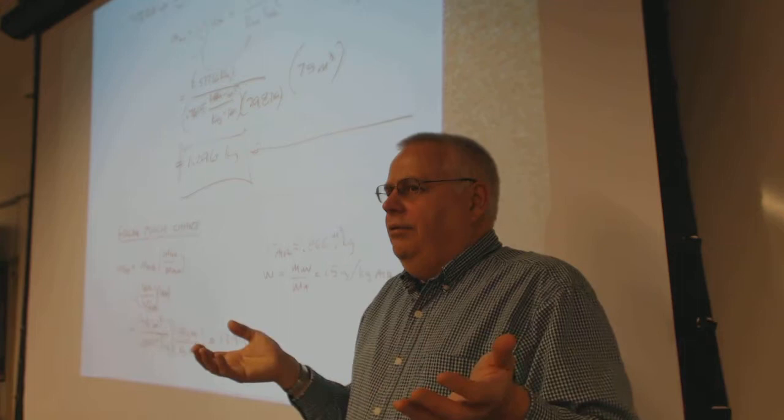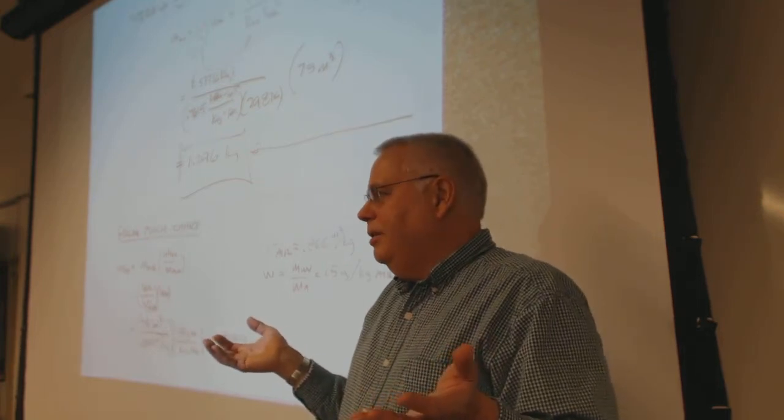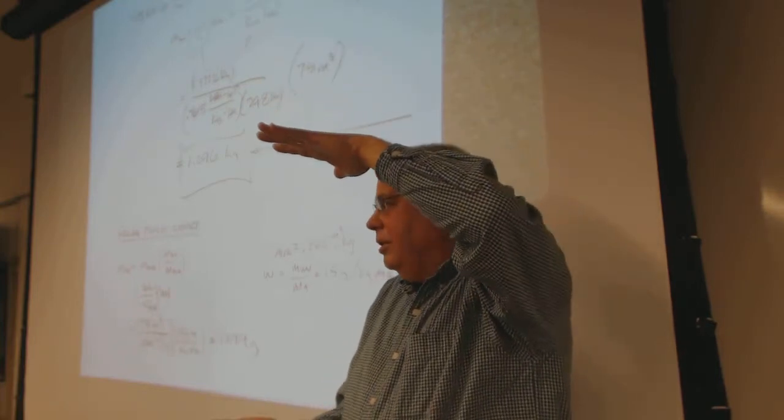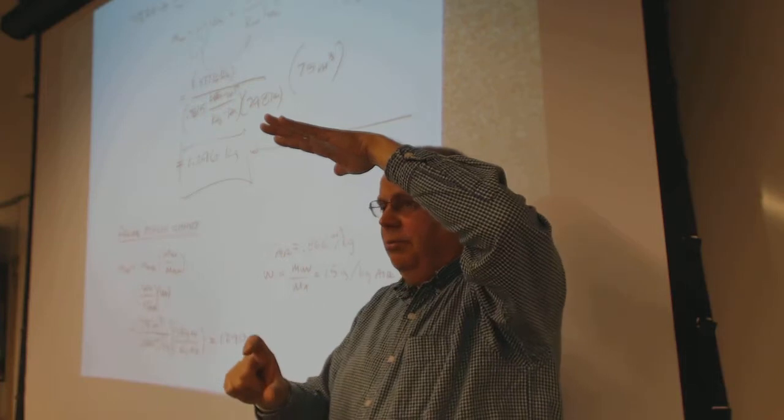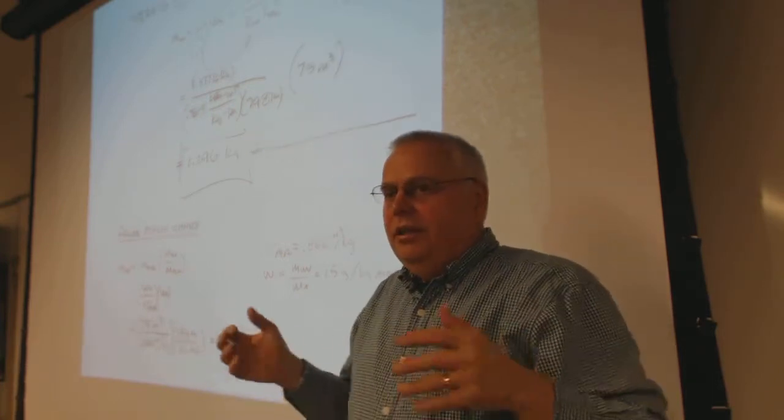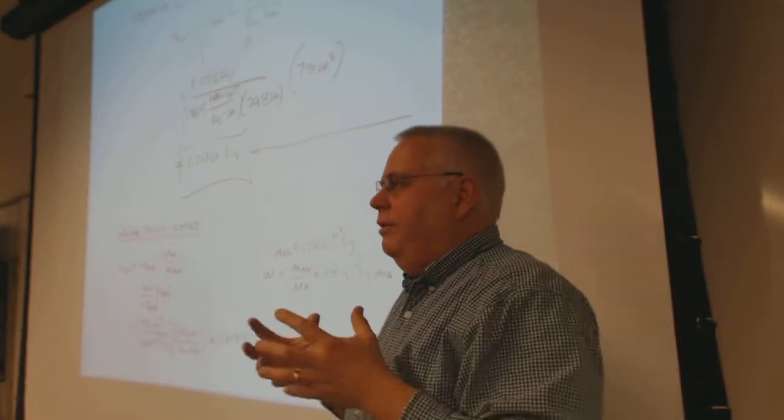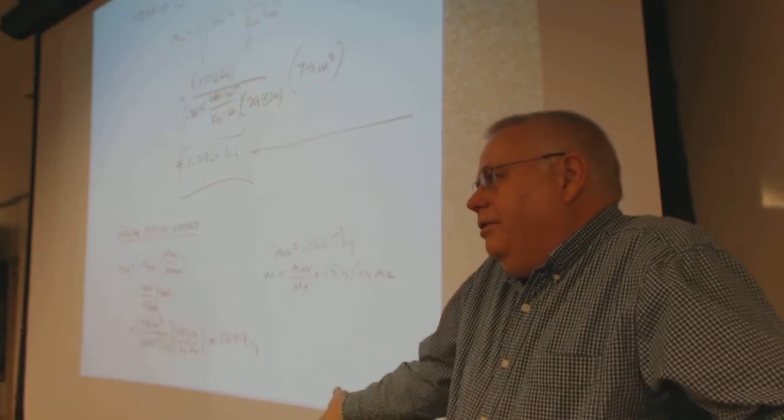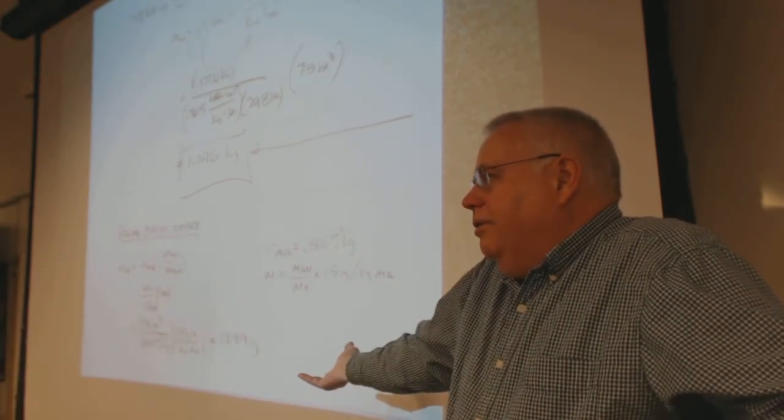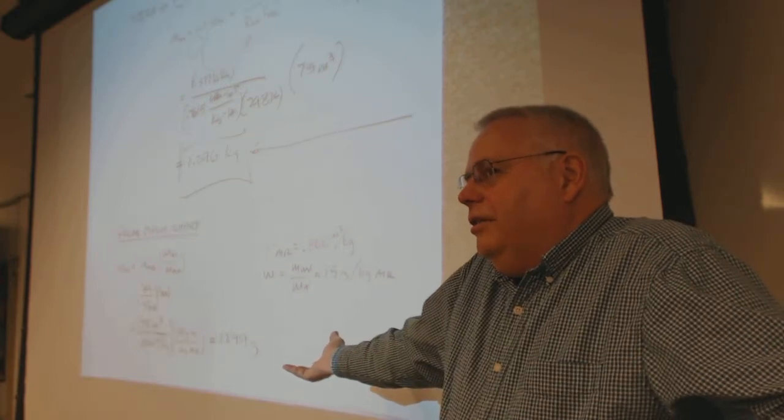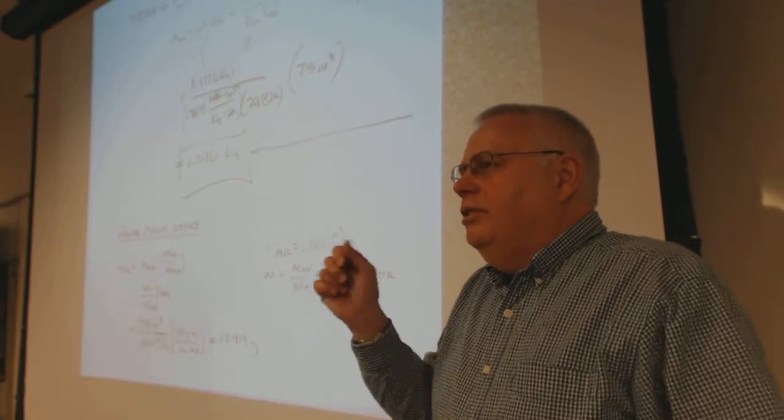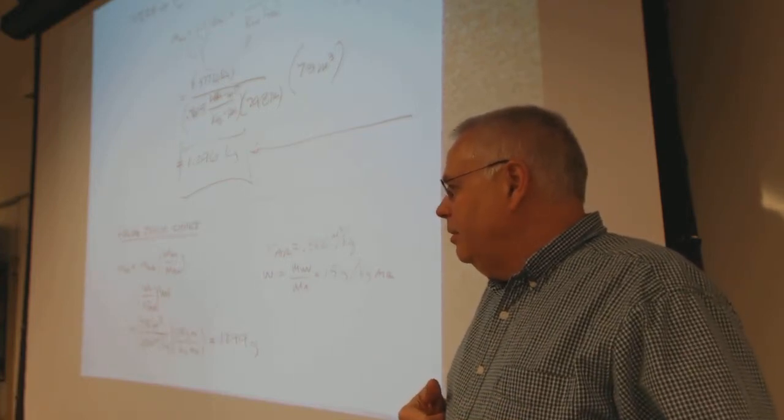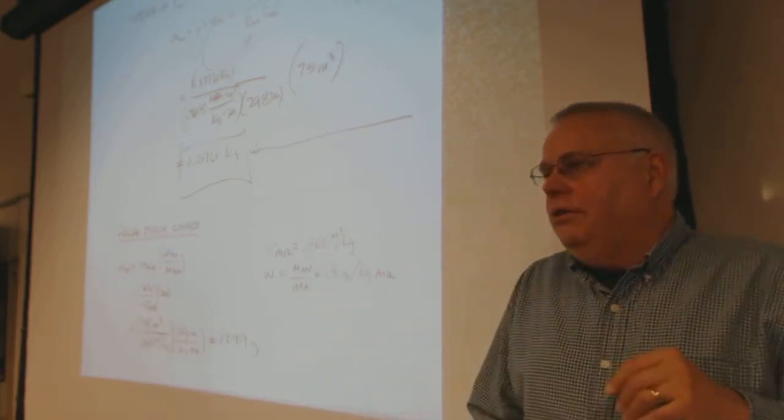Because, you know, you're in Denver, mile high, you might better be using the 6,000 foot chart. What does that mean? Your atmosphere, your total pressure is less. So, the partial pressure of the water is proportionally more, and it sort of squishes the scales on the chart a little bit. The water vapor thing stays the same, the total pressure changes. Even here, we're at 1700 feet, we should be using the 2,000 foot one to actually get more accurate, because, you know, we don't get 101 kilopascals. When we're doing thermal things, there's like 95, 97 kilopascals, the actual pressure in the room here. So, that's probably more like a 2,000 foot elevation.